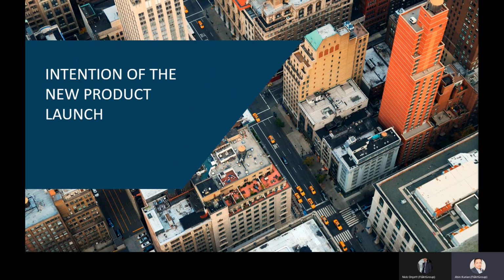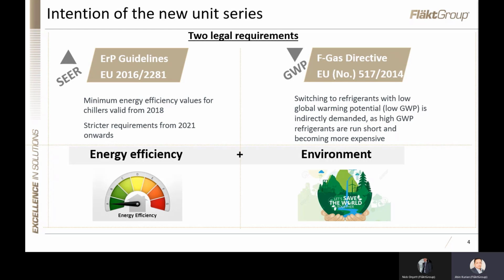In the last year, we have come up with lots of new chiller models, and there was a reason behind it. The new launches are based on two legal requirements. The first is the ERP regulation, ERP 2021, which is related to energy efficiency and demands a higher SEER value. SEER stands for Seasonal Energy Efficiency Ratio, which is an efficiency calculation considering the part load performance of the chiller.